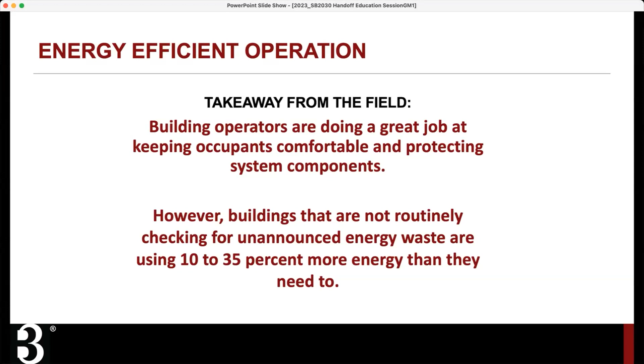Well, how does that happen? Here's a hypothetical energy curve of a new building. Energy consumption is on the y-axis on the left, and the red line indicates energy use over time. A new building is delivered, and ideally it will have been well documented and commissioned using an effective commissioning process, so in theory it's using as little energy as possible to perform those intended functions. But immediately things start to change - set points get altered, dampers may get stuck, actuators break, things fail, adjustments are made, and energy use tends to go up over time.